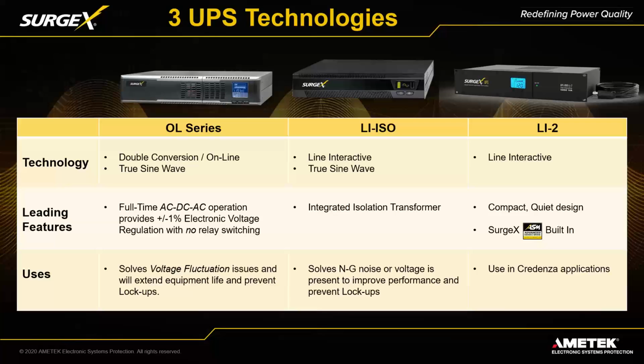But we brought it down from 10 and 15 kVA single phase large format, very bulky units, to something you can put in the rack with an integrated isolation transformer, reestablishing that neutral to ground bond to help mitigate the issue that Envision helped us find.